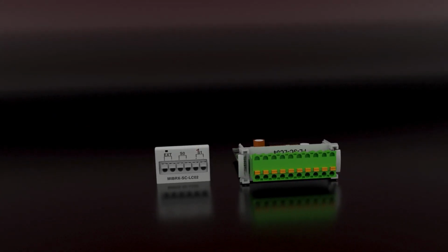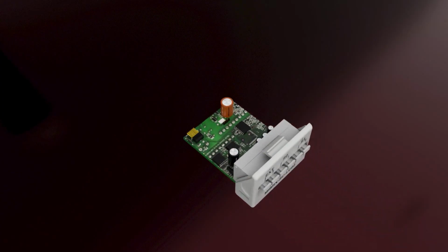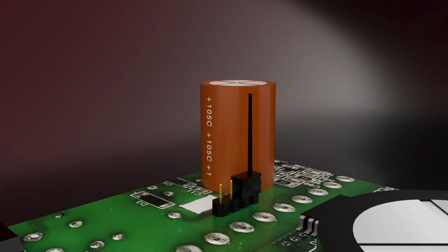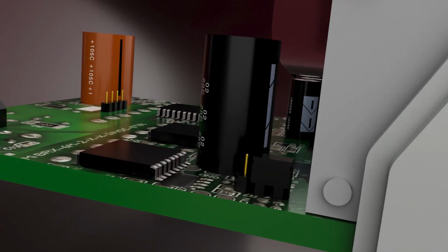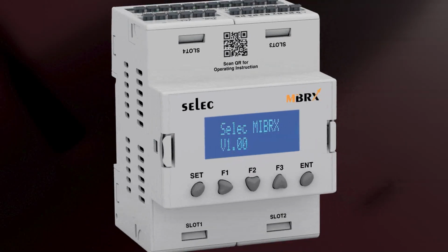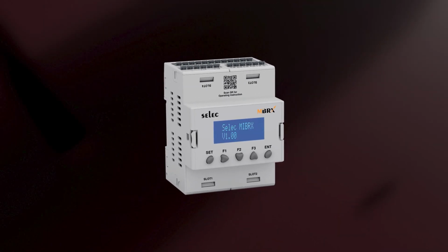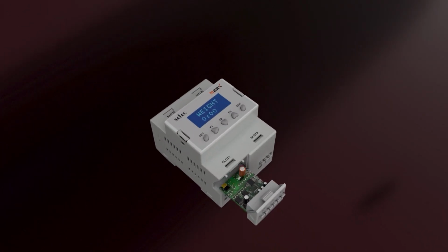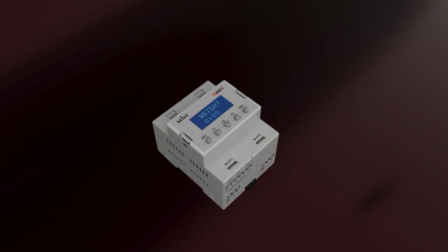Selec offers a 24-bit load cell solution, in the MiBRX and Flexi series, delivering high accuracy, selectable gain settings, and configurable 5V or 9V excitation via jumper selection. This video demonstrates the configuration process using the MiBRX 4M. The load cell card is designed to slide into the PLC slot, and lock securely with a gentle press.